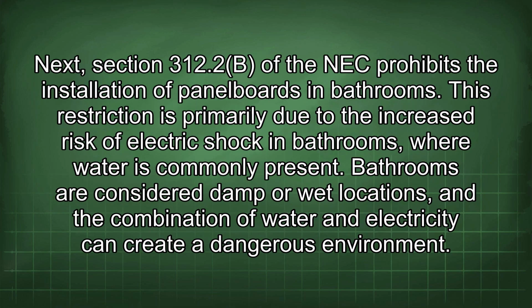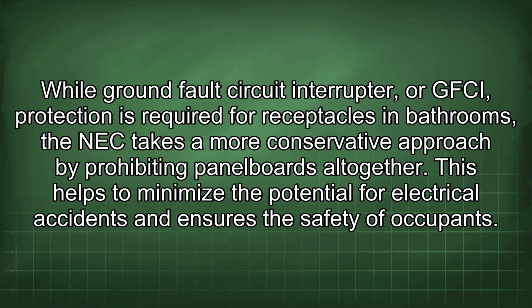Next, Section 312.2b of the NEC prohibits the installation of panelboards in bathrooms. This restriction is primarily due to the increased risk of electric shock in bathrooms, where water is commonly present. Bathrooms are considered damp or wet locations, and the combination of water and electricity can create a dangerous environment. While ground fault circuit interrupter, or GFCI, protection is required for receptacles in bathrooms, the NEC takes a more conservative approach by prohibiting panelboards altogether. This helps to minimize the potential for electrical accidents and ensures the safety of occupants.